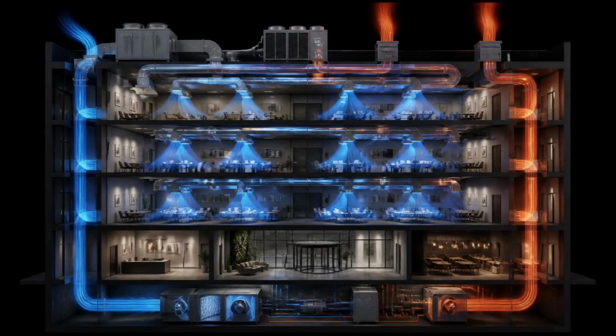We have traveled a long way together tonight. We began outside in the still night air, watching as the building drew its first quiet breath through louvers set into its walls. We followed that air inward, through filters and air handlers, across coils that quietly changed its temperature, and into the long and branching network of ducts that carry it to every corner of the building. We watched as VAV boxes made their gentle adjustments, opening and closing in small, deliberate movements to give each space exactly the amount of air it needed.